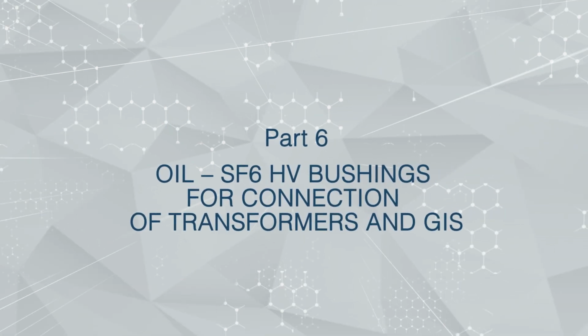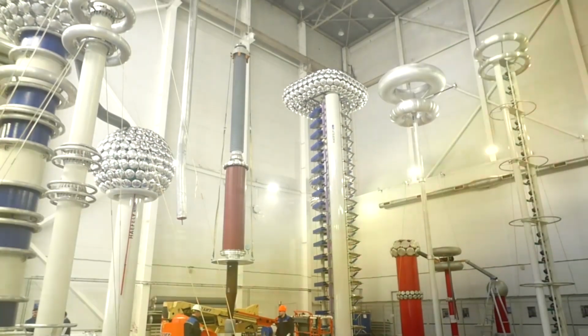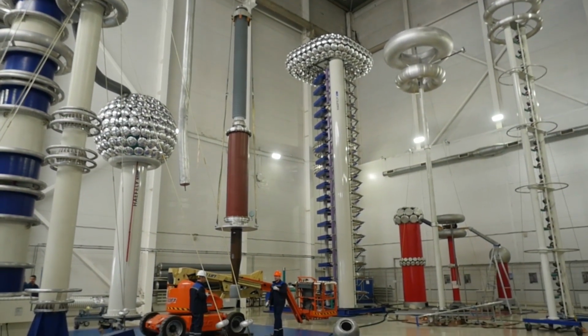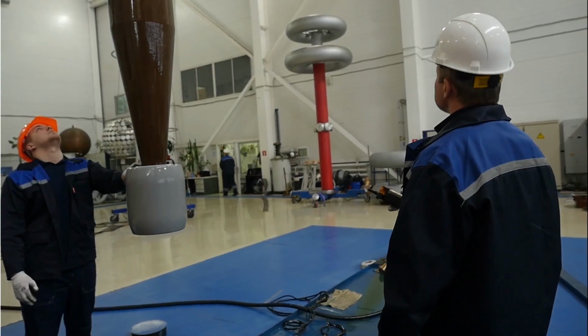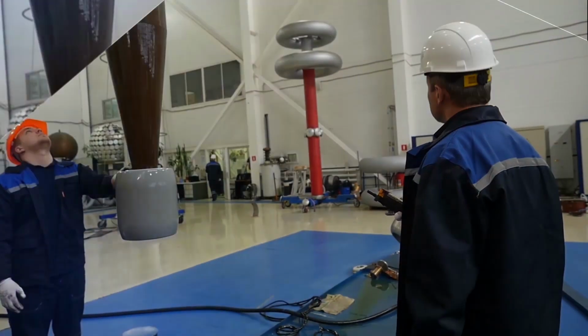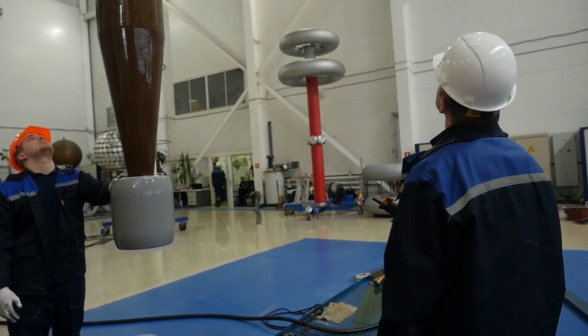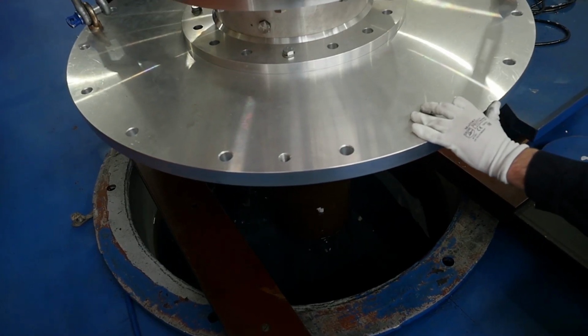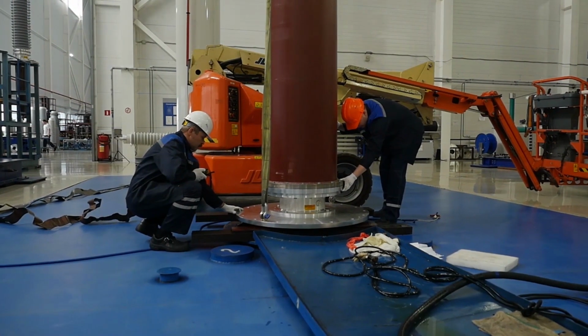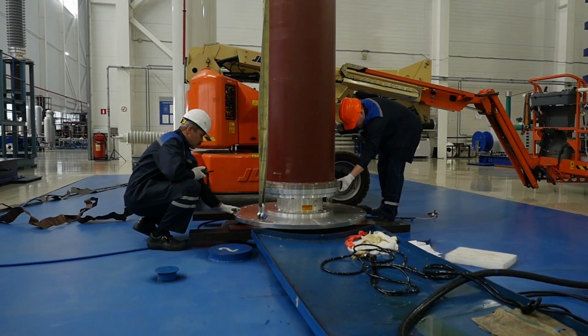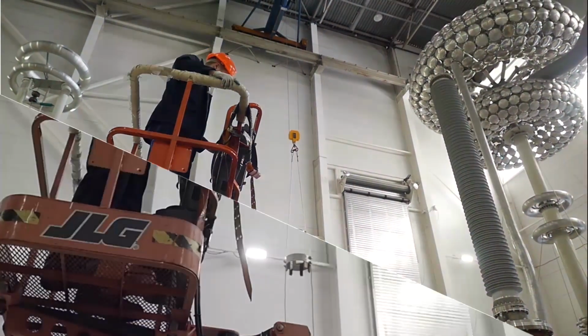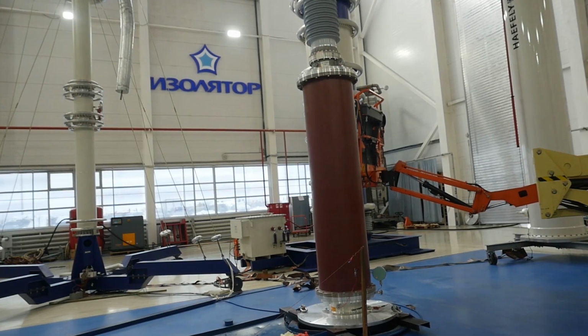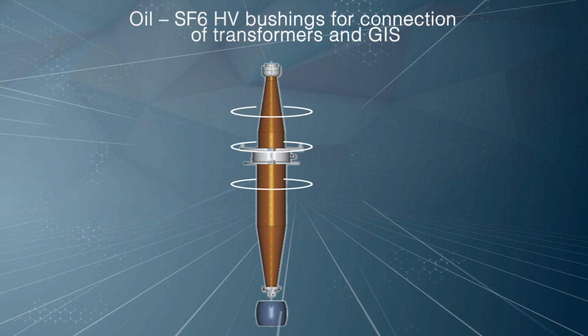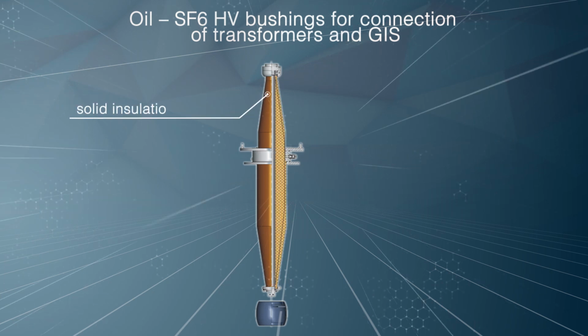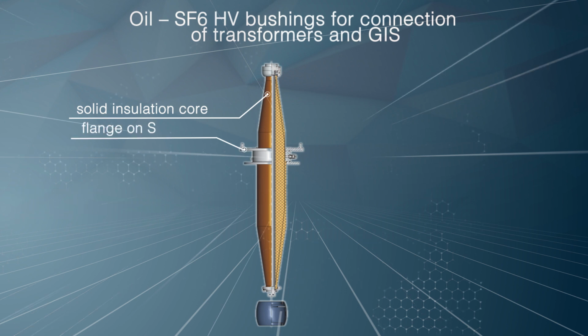Oil to SF6 high-voltage bushings for connection of transformers and GIS. These bushings were developed in recent years. Bushings of this type are feed-through insulators intended for separating two insulating media, SF6 gas and oil, in an airtight switchgear when connecting it to a transformer. In operation, the bottom part of the bushing is inside the transformer tank in the transformer oil medium, while the upper part is in the cover of the SF6 gas compartment. The bushings of this type are characterized by the absence of external insulation both on the bottom and top parts.